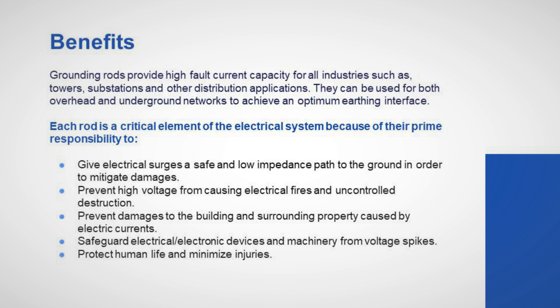Benefits: Grounding rods provide high fault current capacity for all industries such as towers, substations, and other distribution applications. They can be used for both overhead and underground networks to achieve an optimum earthing interface. Each rod is a critical element of the electrical system because of its prime responsibility to give electrical surges a safe and low impedance path to the ground in order to mitigate damages.